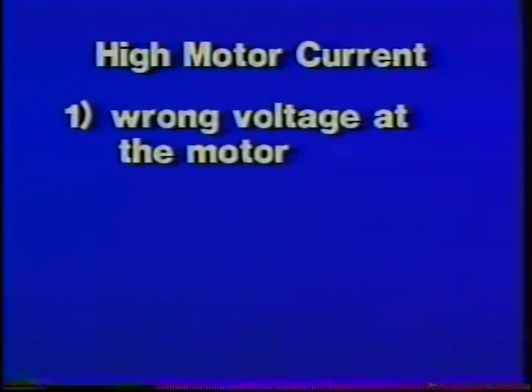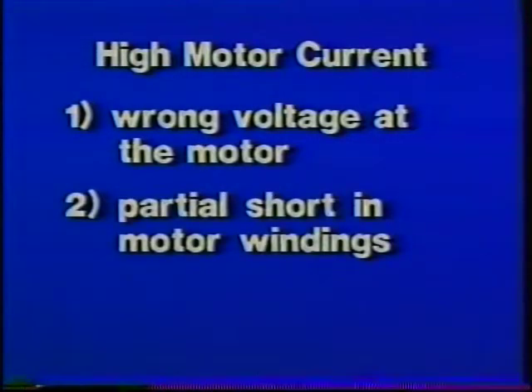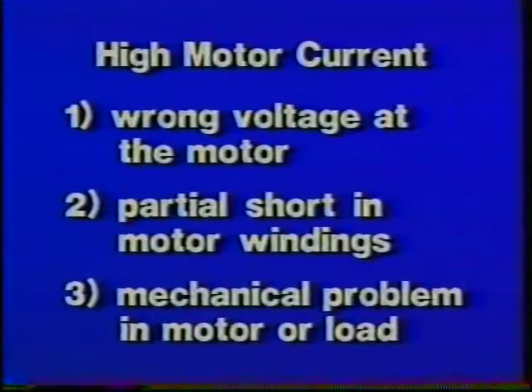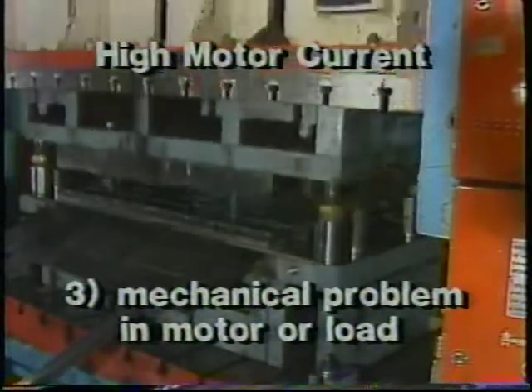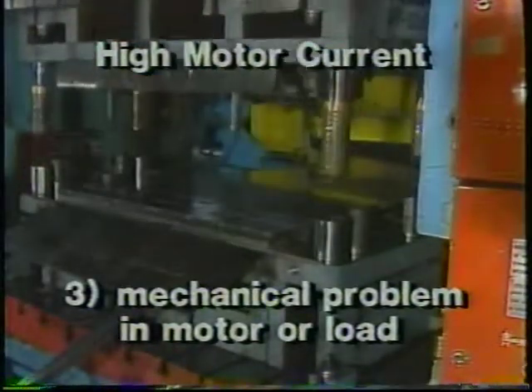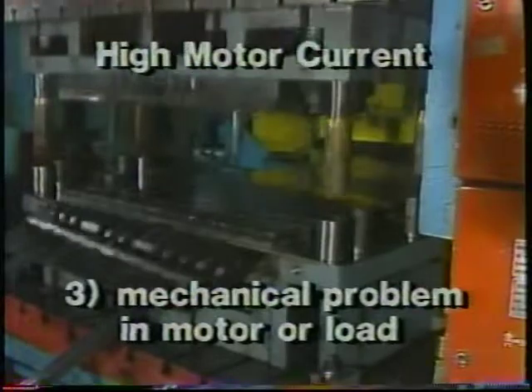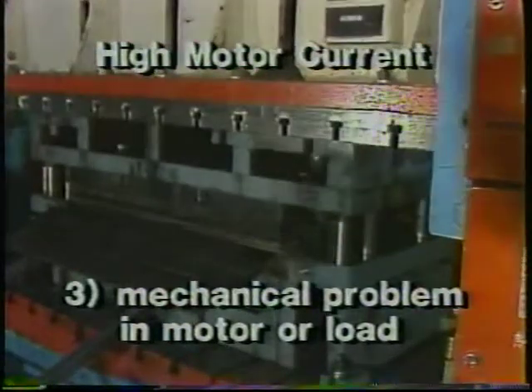Voltage at the motor may be low or high. There also might be a partial short in a motor winding, bad enough to increase motor current, but not enough to keep the motor from starting up. Or something may be dragging in either the motor itself or the load. Dry or worn bearings, bent and rubbing parts, dull cutting tools, or too heavy a load on the equipment, all will increase motor current.